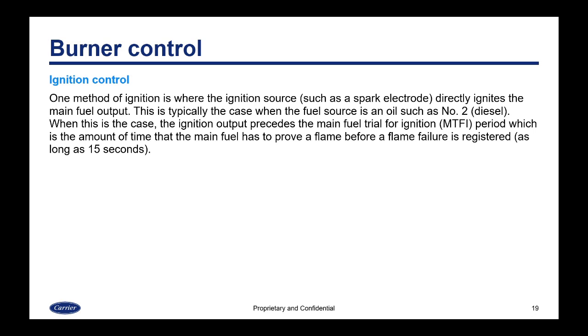One method of ignition is where the ignition source, such as a spark electrode, directly ignites the main fuel output. This would typically be the case when the fuel source is an oil such as number two. When this is the case, the ignition output precedes the main fuel trial for ignition period, which is the amount of time that the main fuel has to prove a flame before a flame failure is registered. This could be as long as 15 seconds.